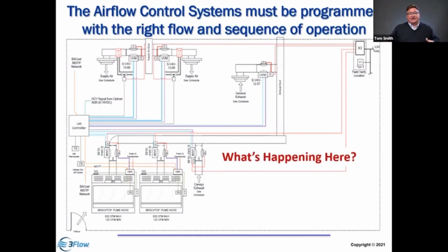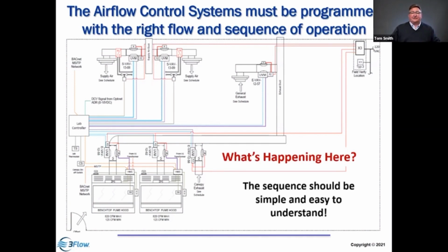What is our expectation? It needs to be clear. We need to have a sequence that's easy to understand. That says something like the hood modulates flow between the sash being closed and the sash open. And when it modulates flow through the hood, it's connected to the air supply, and it tracks in tandem. You close the sash, the flow goes down. Open the sash, the flow goes up. Should be that simple. A complicated diagram like this may be important for installation and maybe for diagnostics, but it's hard for a hood tester to understand.